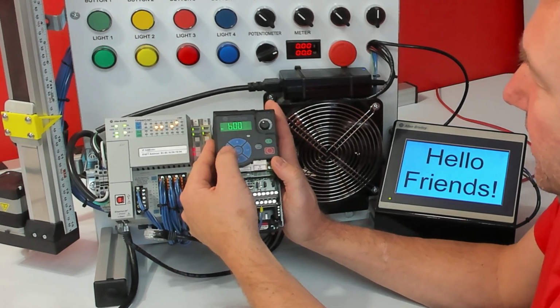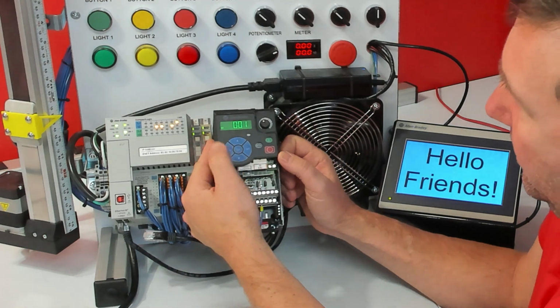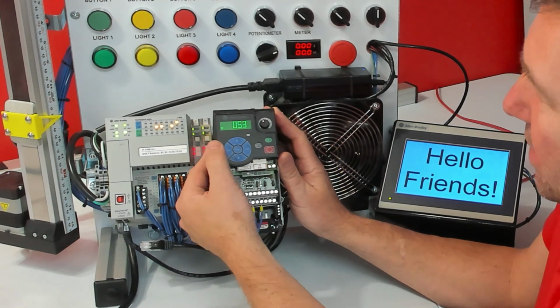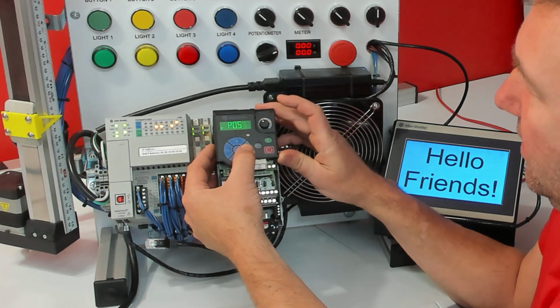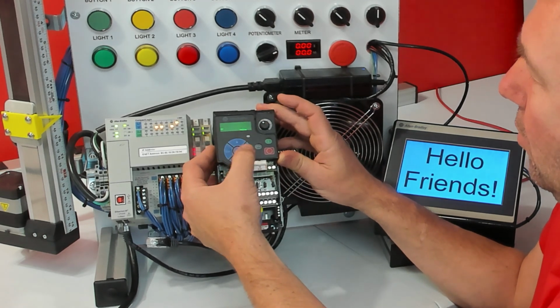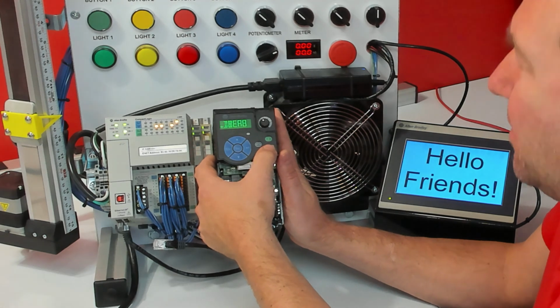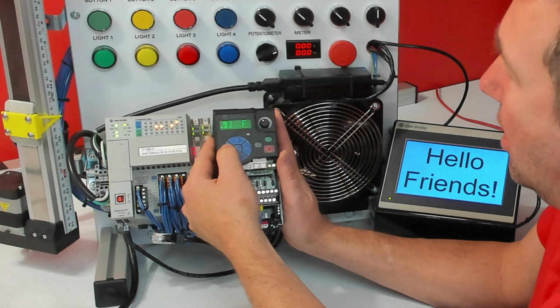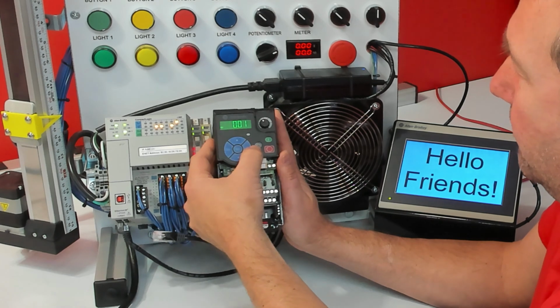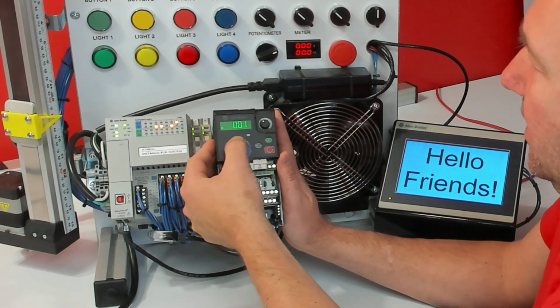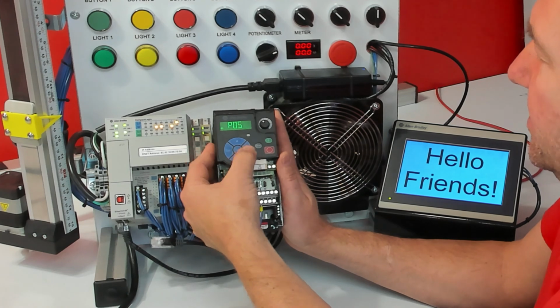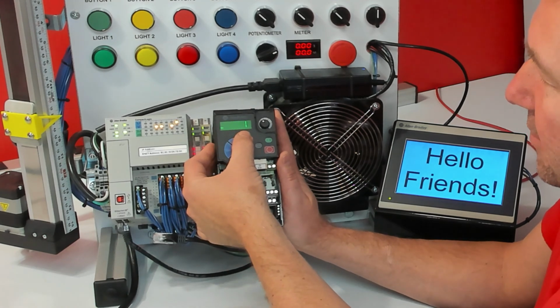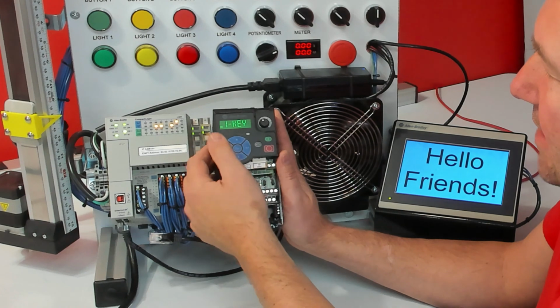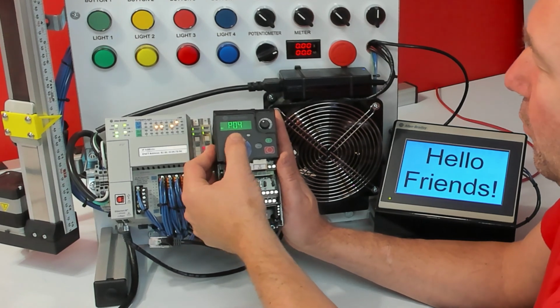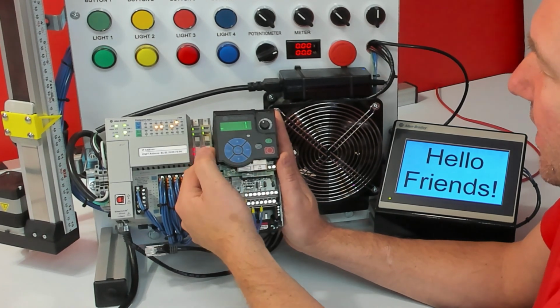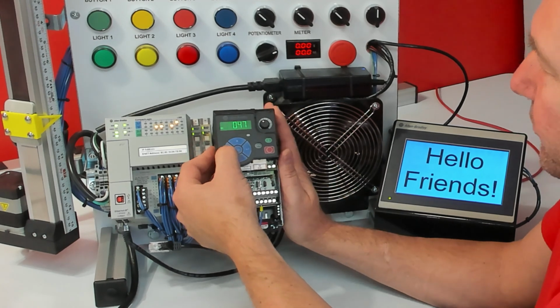Now I'm going to hit the escape button to go into my parameters. I'm going to hit it again to highlight the B and go up to P. And we're going to be looking for 53, and I'm going to set it to 1. And a value of 1 resets most of its operating parameters, which is going to include P46 and P47. So now if I go to P46, it's no longer on Ethernet IP. It's on the keypad. And also P47 is now on the potentiometer here.